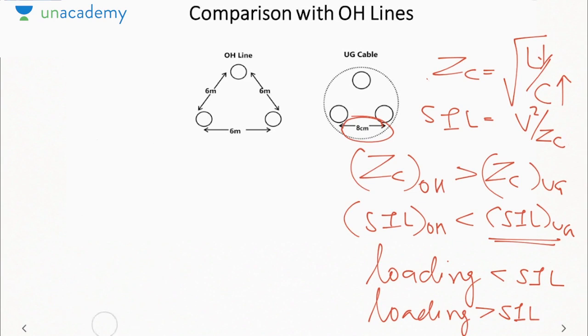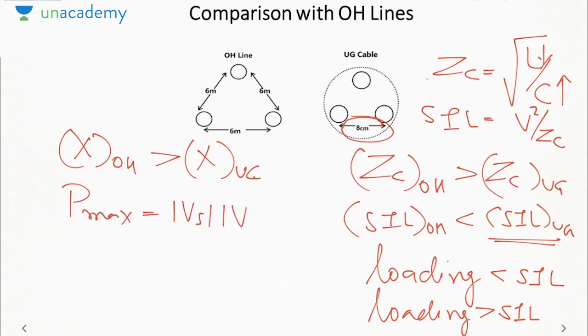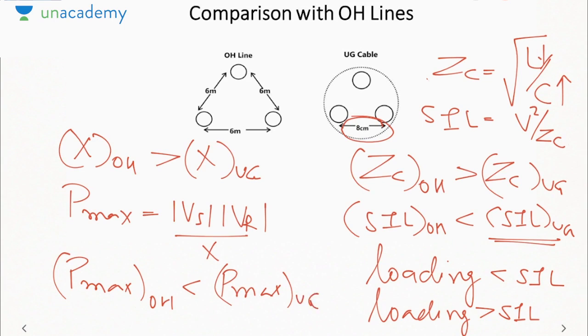Then since the inductance is reduced, I can say the reactance of overhead line is greater than the reactance of UG cable. Now we saw maximum power is given as mod Vs mod Vr by X. Since reactance of UG cable is less, its Pmax would be high. That means the steady state limit is also high in case of UG cable. Now since steady state and SIL limits are very high in case of UG cable, the critical design criterion that decides the loading is the thermal limit. Because these limits have been exceeded but not the thermal limit, loading is only decided on the basis of thermal limit in case of underground cable.